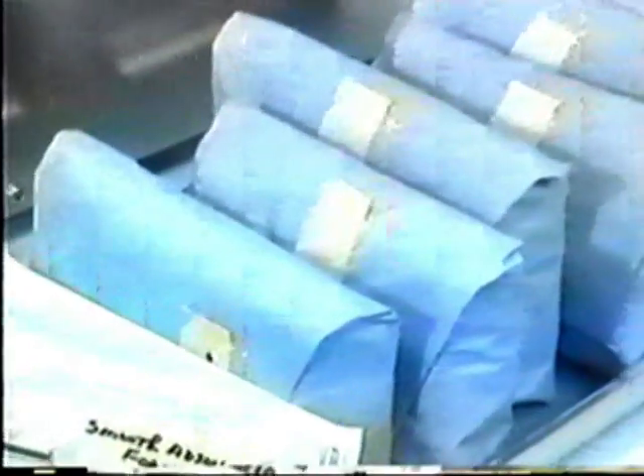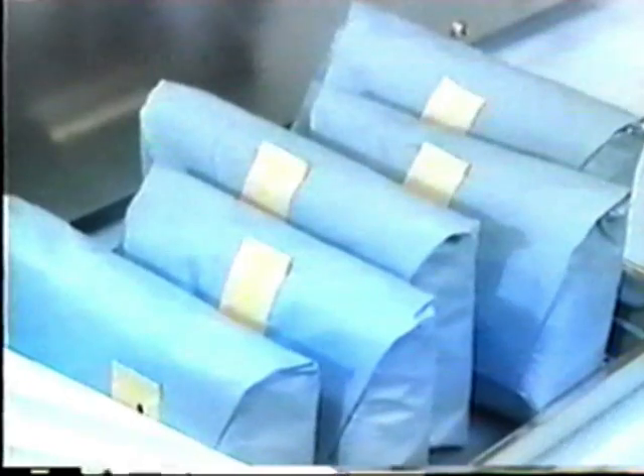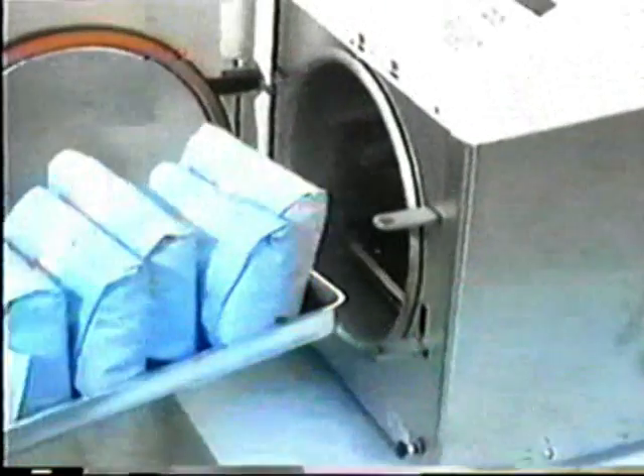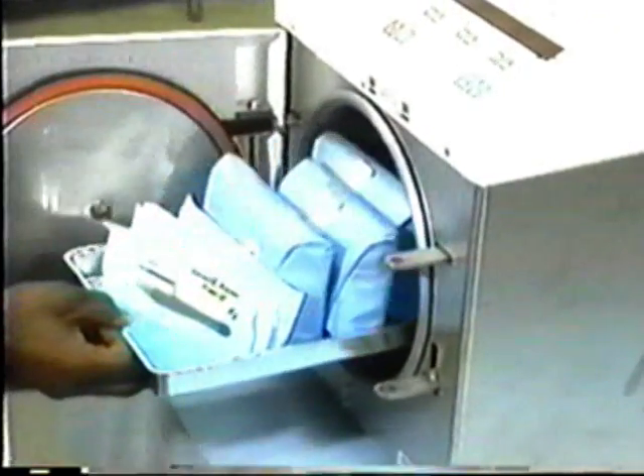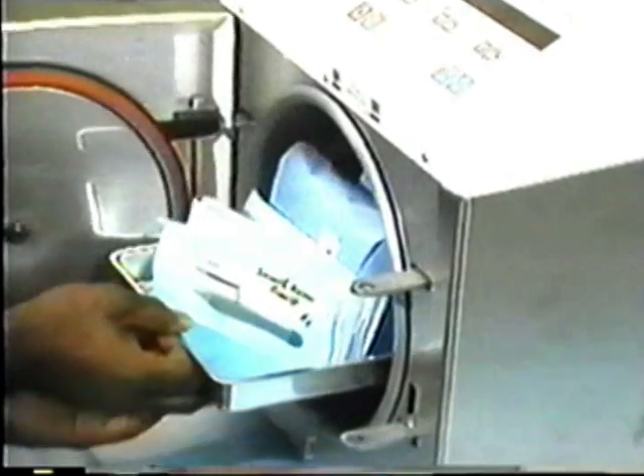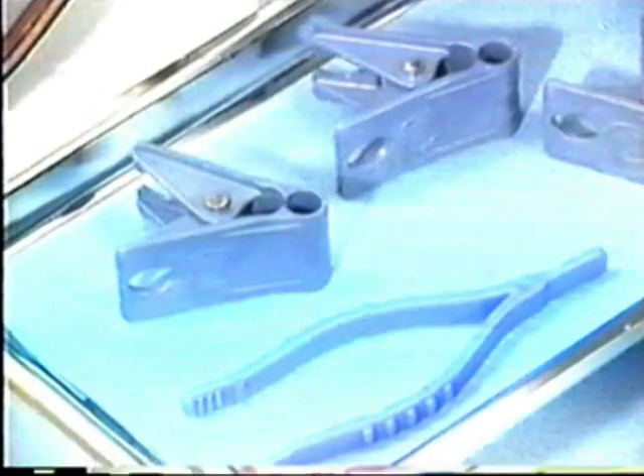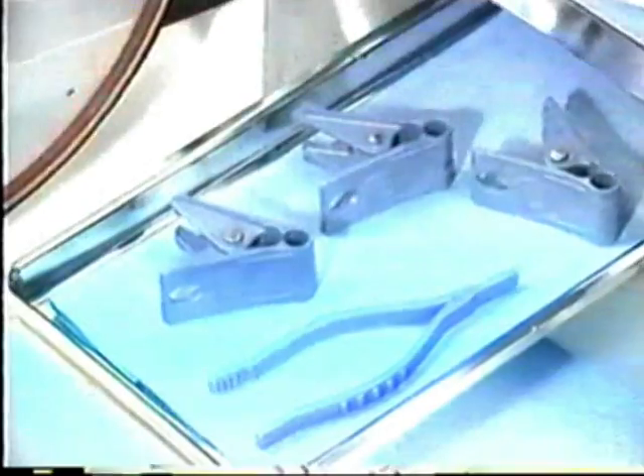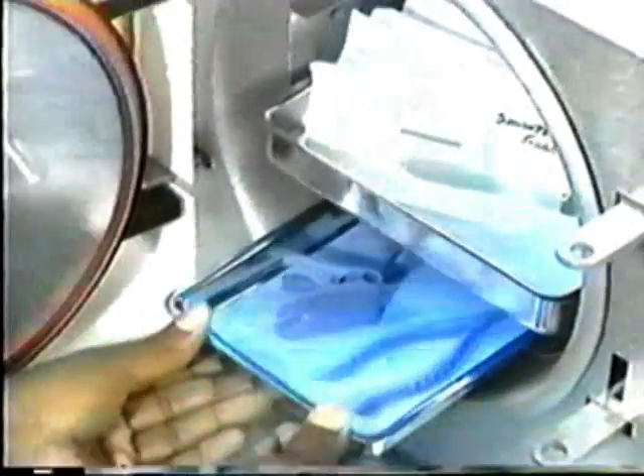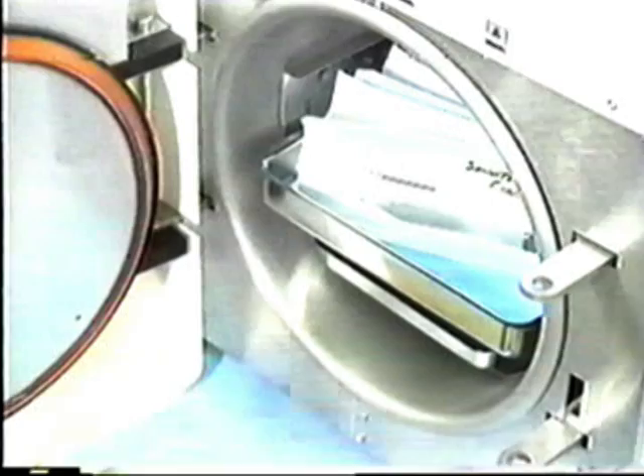Items wrapped in disposable paper bags are placed horizontally on their sides in the sterilizer tray. Place linen and dressing packs in a vertical position. When sterilizing linen packs and hard items in the same load, place the linen packs on top. This prevents water condensation from dripping down on the linen packs. No item should rest against plastic utensils. Otherwise, they may not retain their shape while being exposed to very high temperatures.